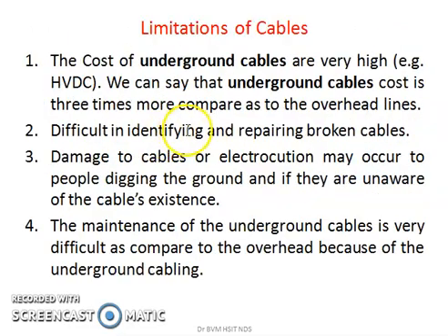Fine. Now coming to what are the limitations of underground cables. The cost of underground cables is very high as compared to that of our overhead transmission line. We can say that underground cable cost is 3 times more than that of your overhead lines for the same capacity. It is difficult to identify and repair broken cables. If there is any fault on the underground cables, it's very difficult to locate the fault.